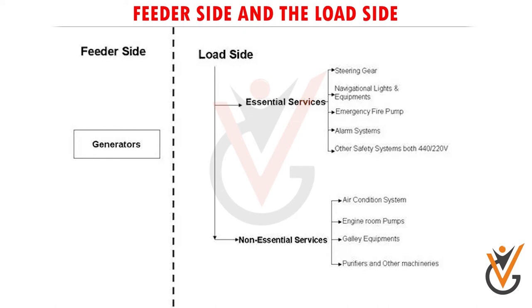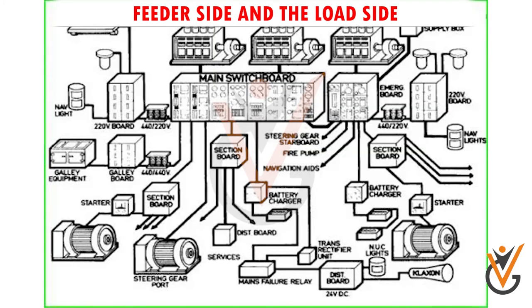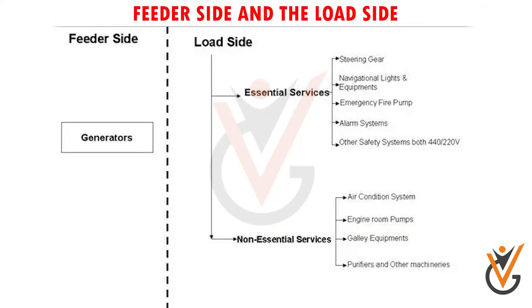Essential services include supply to navigational aids like radars, communication equipment, navigational lights, and steering gear motors. These essential services may be supplied directly from the main switchboard or via sectional boards or distribution boards. Non-essential services are those that do not affect the safety of the ship and personnel — for example, air conditioning compressors and fans.